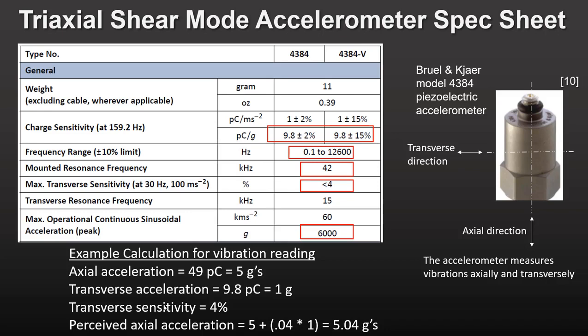The accelerometer will pick up a small amount of transverse vibrations when measuring vibration in its axial direction. This is shown in the diagram on the right side of this slide and in a specification called max transverse sensitivity, which is typically measured at only one frequency — 30 Hz in the case of this sensor. This means the axial acceleration you measure will be a combination of both axial and transverse accelerations. For example, if the actual axial acceleration were 5 g's, which would be a charge of 49 picocoulombs, and the transverse sensitivity is 4 percent, the accelerometer would tell you the axial acceleration is 5.04 g's, not 5 g's.